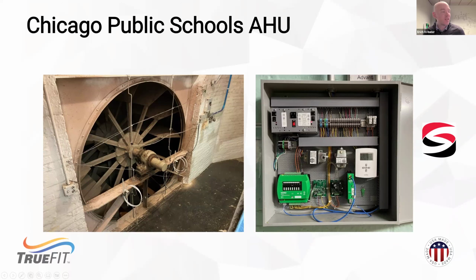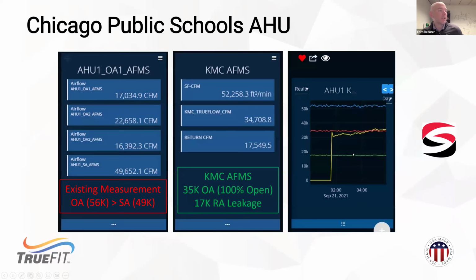And the results of that installation were, we have the Ebtron existing measurements on the left, KMC or the TrueFit measurements in the middle. Looking at the outdoor airflow measurements that were existing, again, we got 3 total, 1 for each damper. We see that one of them is a lot higher than the other. We had the same balancer that commissioned these come out and commission ours.